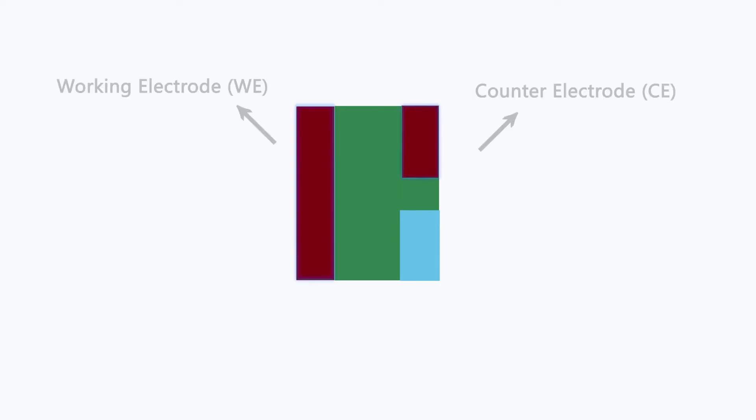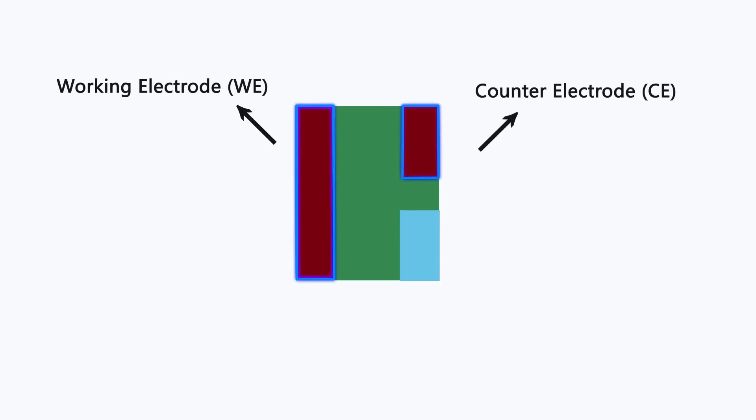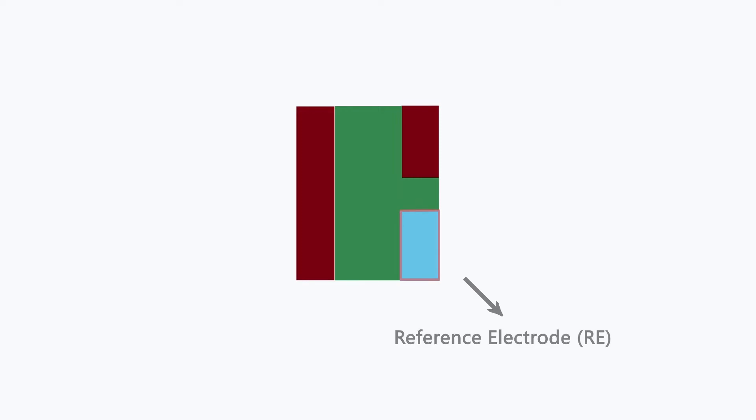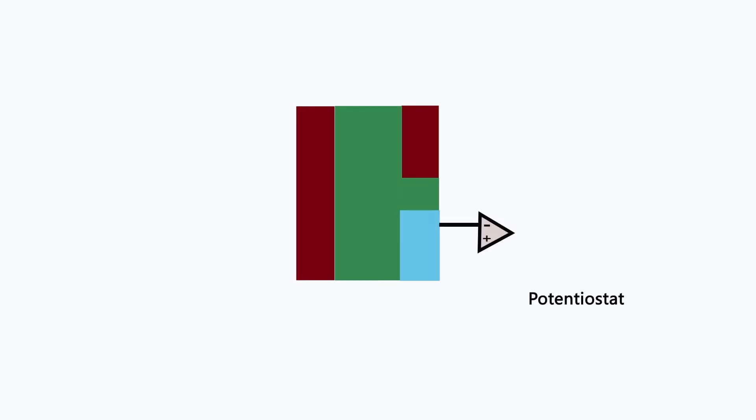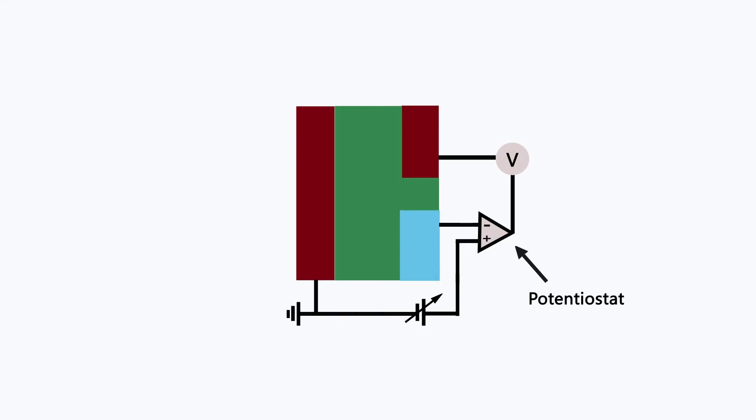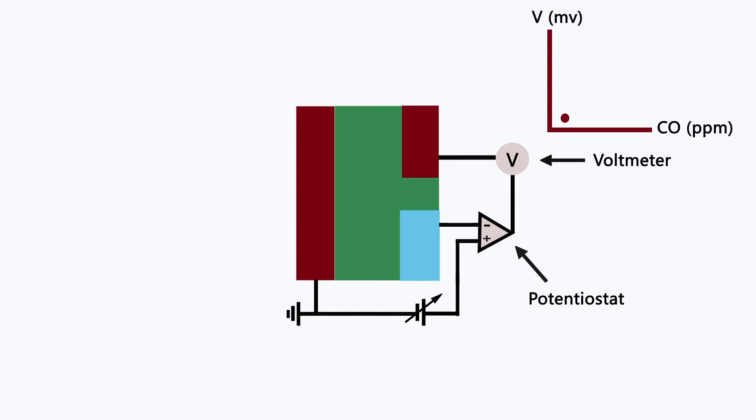Since the reactions occurring at both electrodes will polarize the electrodes, which makes it difficult to maintain a constant potential between them, this carbon monoxide sensor is fitted with a reference electrode. For a three-electrode electrochemical gas sensor, its output reflects the change in potential between the reference electrode and the working electrode. The reference electrode can provide a stable electrochemical potential in the electrolyte, because it does not participate in the electrochemical reaction. Therefore, the potential change is directly related to the concentration change of the measured gas.